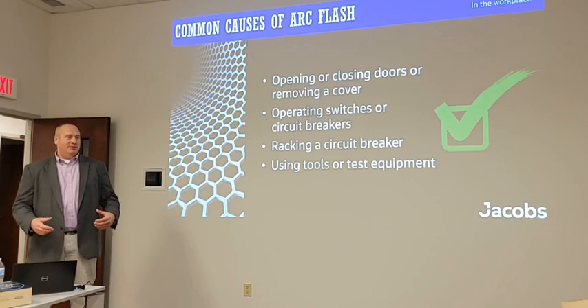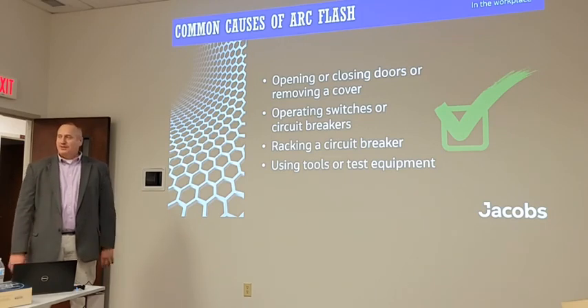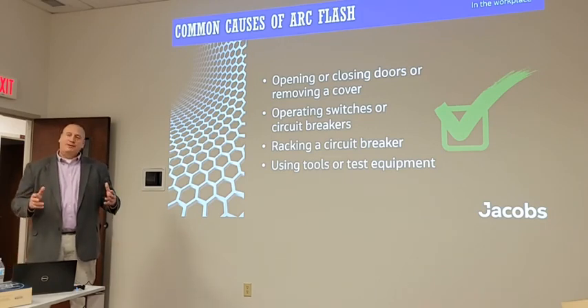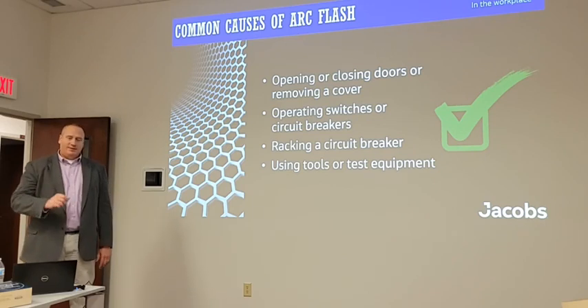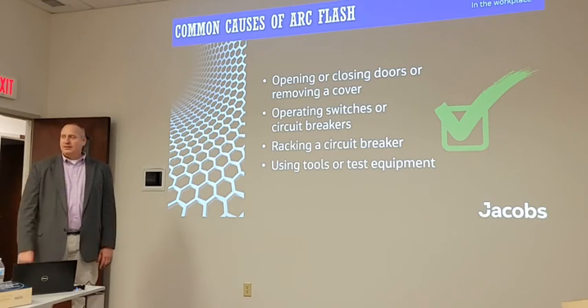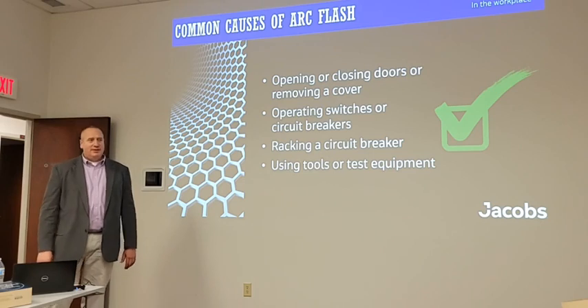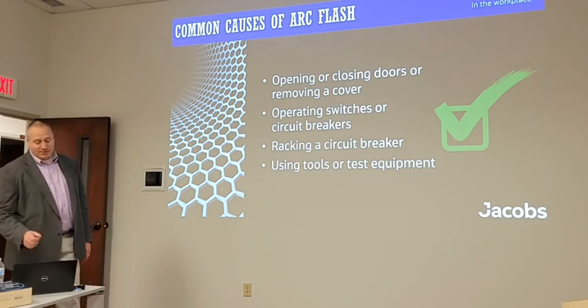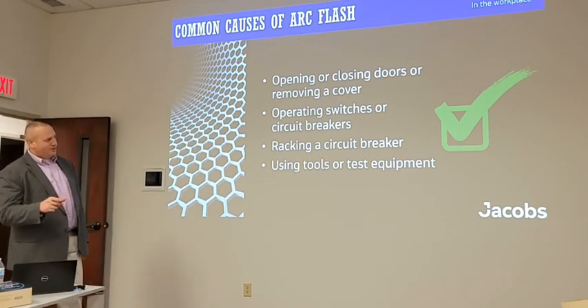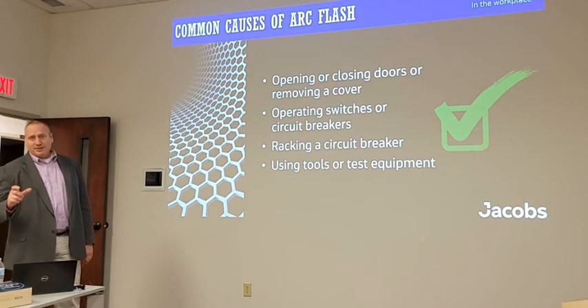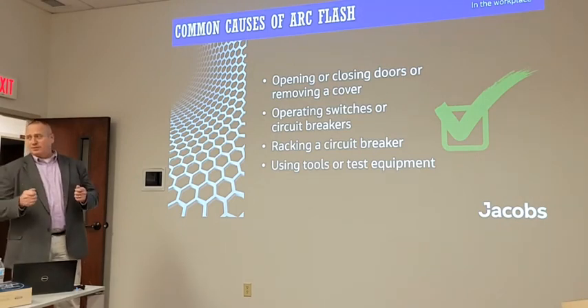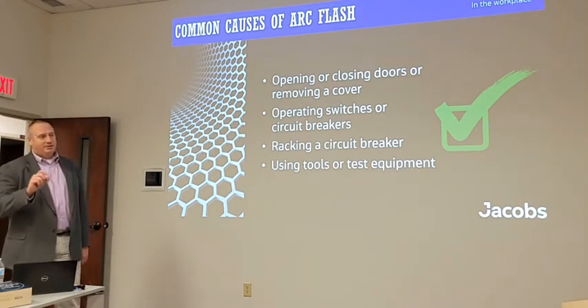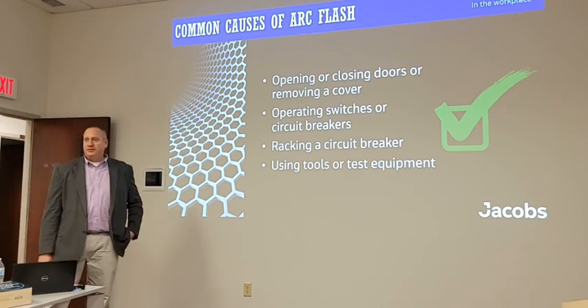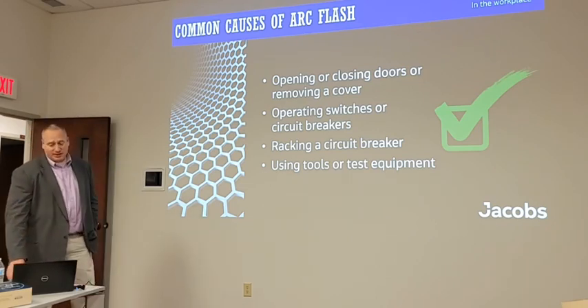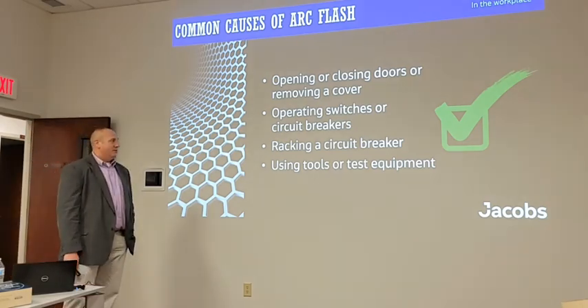And so you're not getting your leads tested like you do your voltage rated gloves. So how much do you want to risk your life on how many times it takes to put a nick in it that's going to come through and shock you? Those voltage rated tools and voltage rated test leads are not so you can hold those barehanded. It's to keep you from inadvertently shorting phase to phase or phase to ground when you're working around energized components.